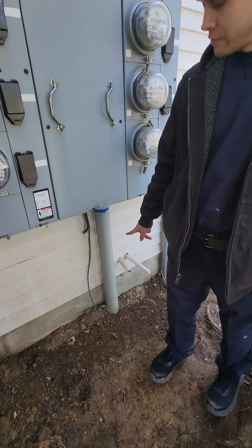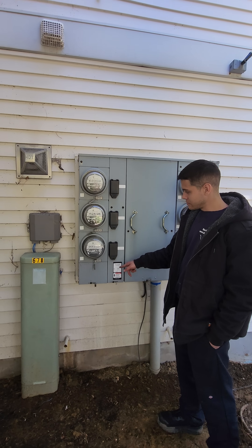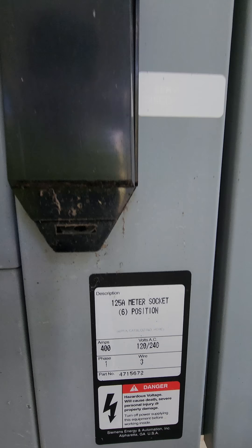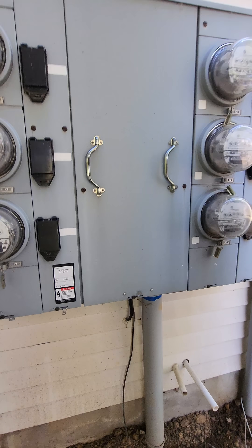I can tell by this pipe this is a 400 amp service coming in just by the pipe size. And right here it says 125 amp meter socket, six position, and 400 amps. Single phase three wire.